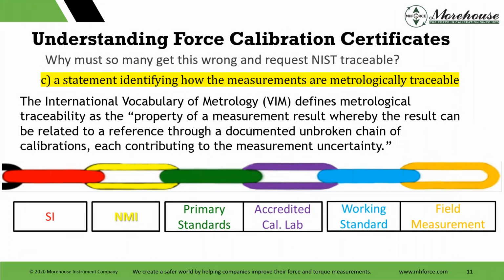When we start talking about identifying how measurements are metrologically traceable, we're talking about the International Vocabulary of Metrology, the VIM, which defines metrological traceability as the property of a measurement result whereby the result can be related to a reference through a documented, unbroken chain of calibrations, each contributing to the measurement uncertainty.